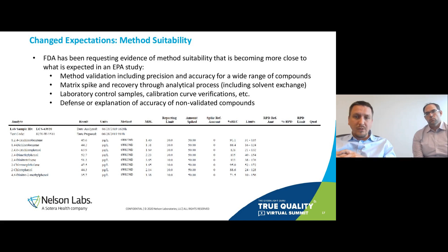At the same time, if you're conducting these studies or planning to conduct these studies, I would expect the lab that you use to be able to provide method suitability data either in their report or make it clear in their report that this information is available to the FDA if the FDA should ask. And that information should include things like method validation for a range of compounds. So there should be a set of surrogates that they've demonstrated accuracy and precision on, matrix, spike, and recovery through the entire analytical process, including liquid-liquid extractions, and so on and so forth.